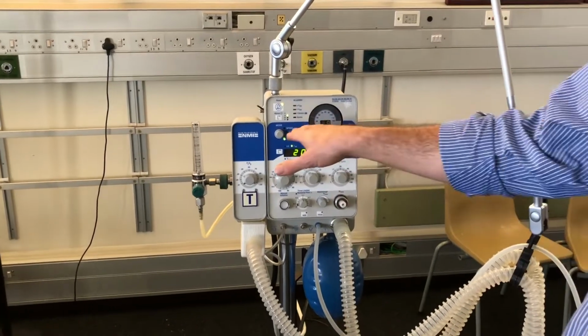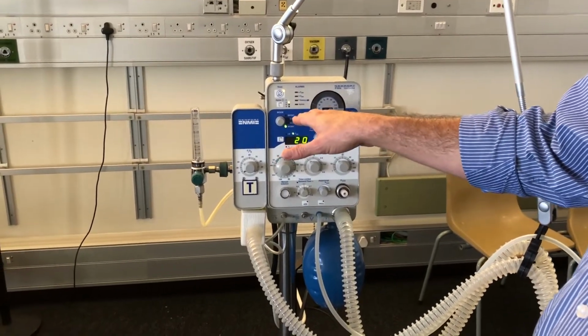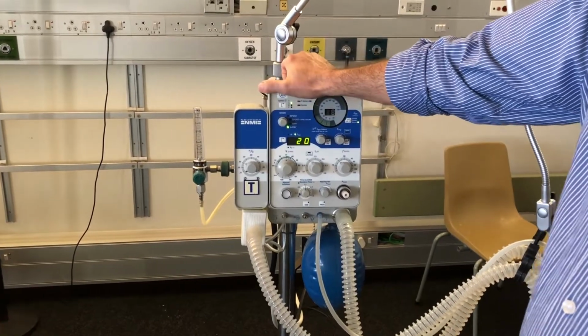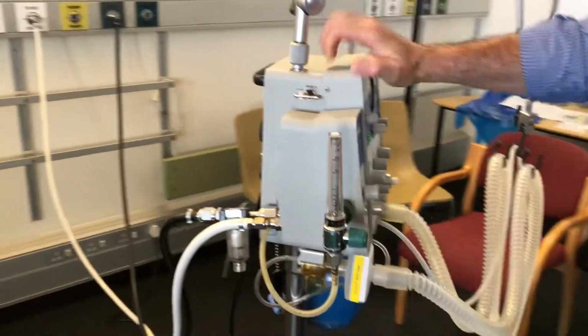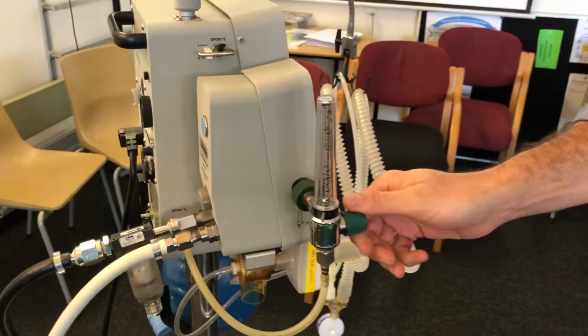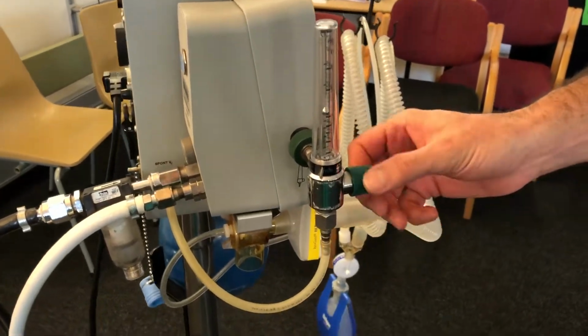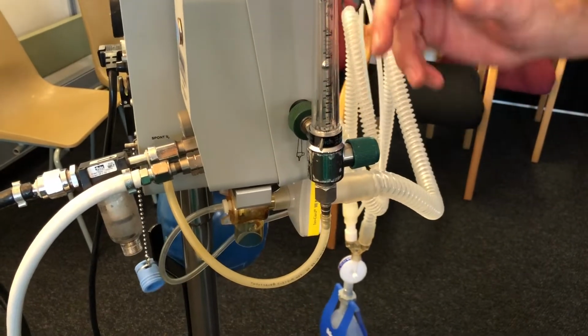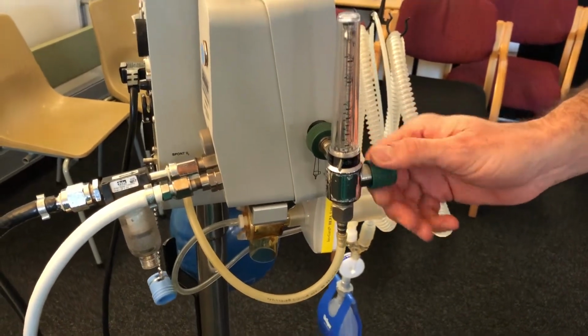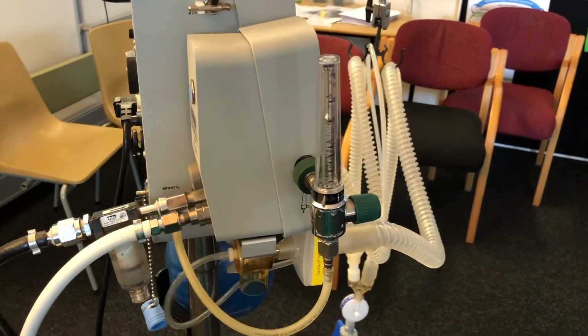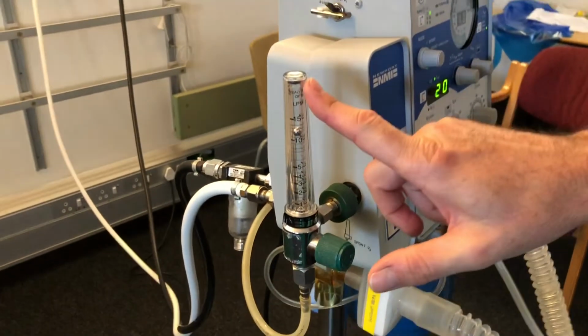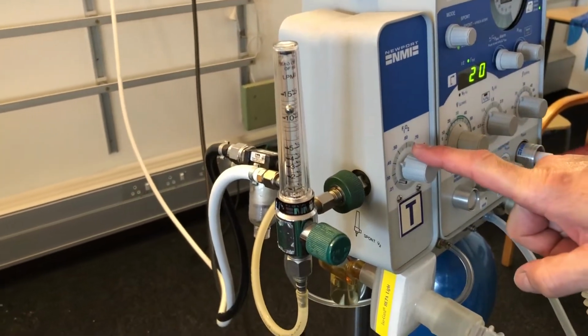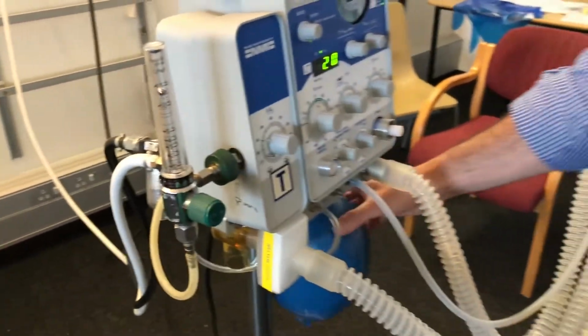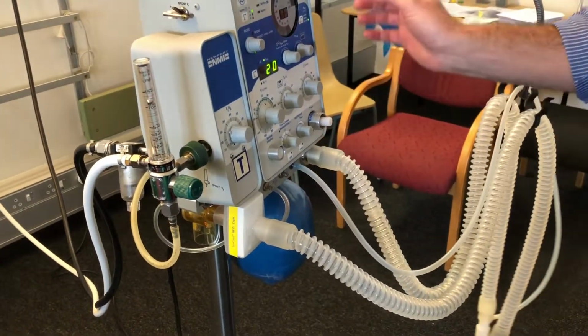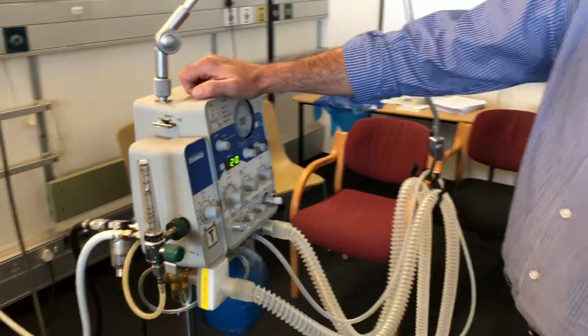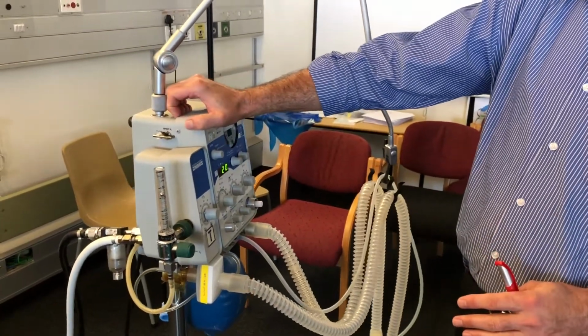So as far as the spont mode goes, there are two sources of gas for the patient to breathe from. The first source of gas is this rotameter, which we can dial from 1 to 15 liters a minute. And when I switch this rotameter on, what the machine will do is it will deliver gas at a preset FiO2 into the circuit and into the reservoir bag. That's the first setting we have in terms of gas supply for a patient breathing spontaneously.